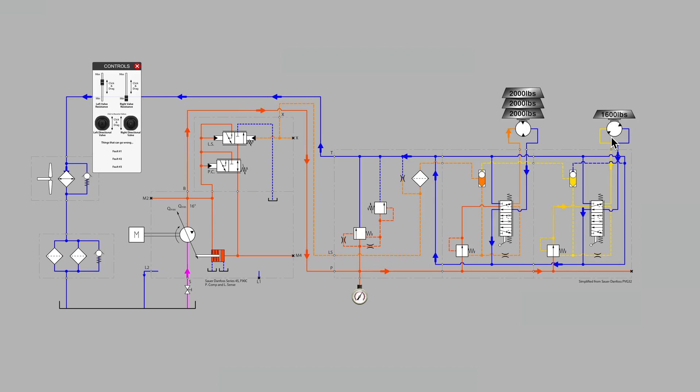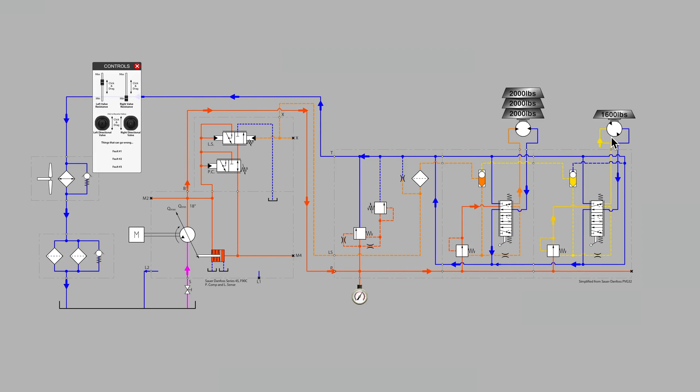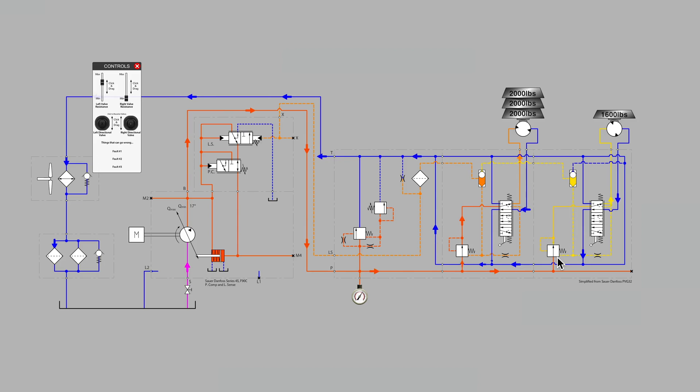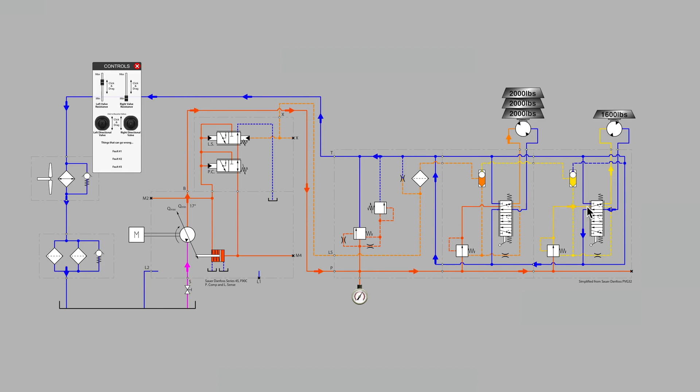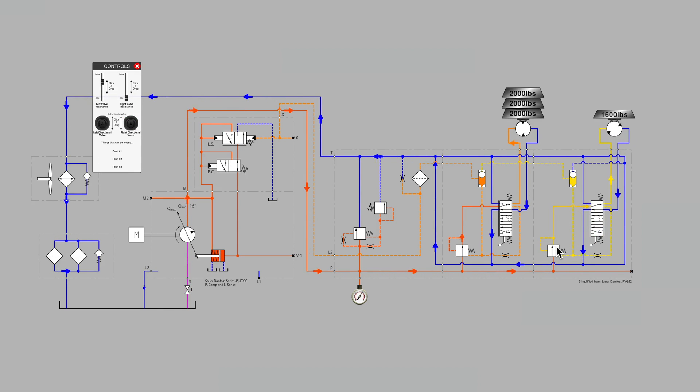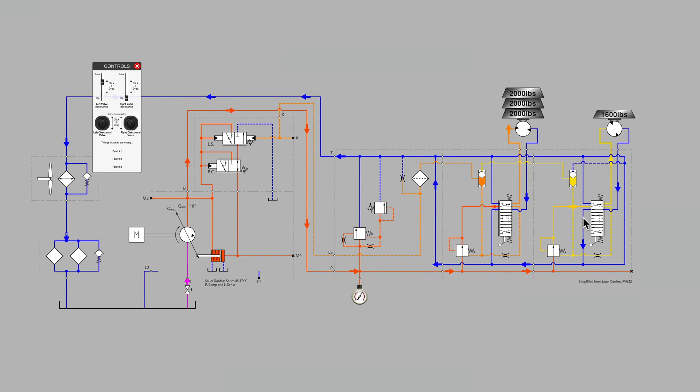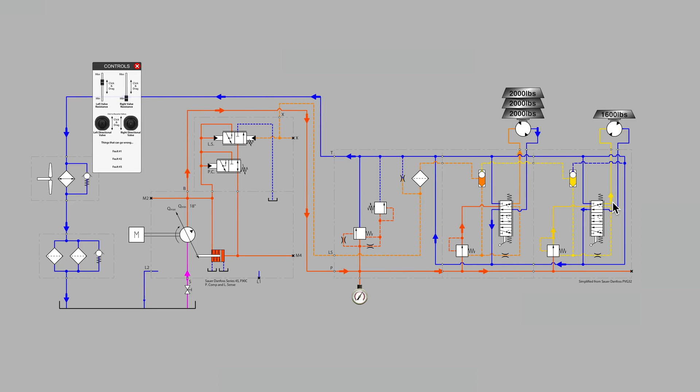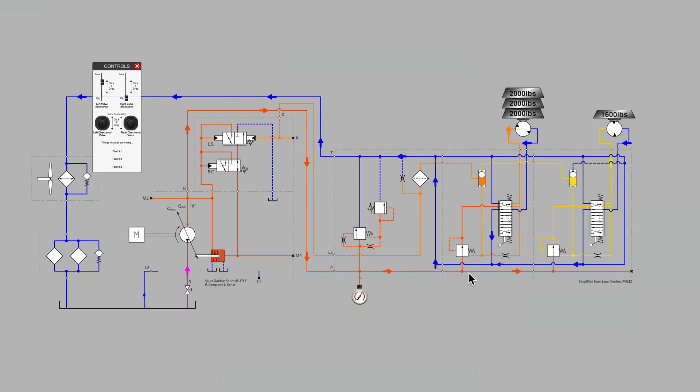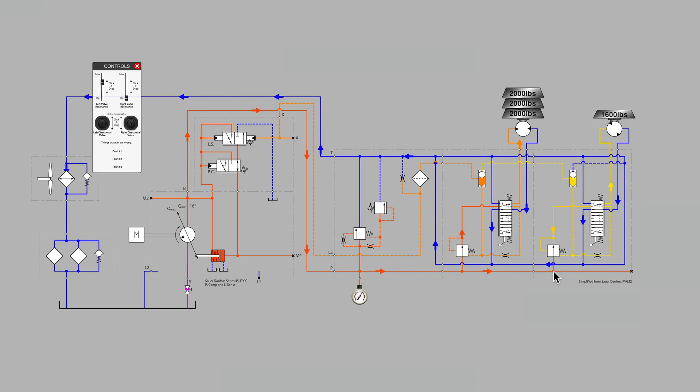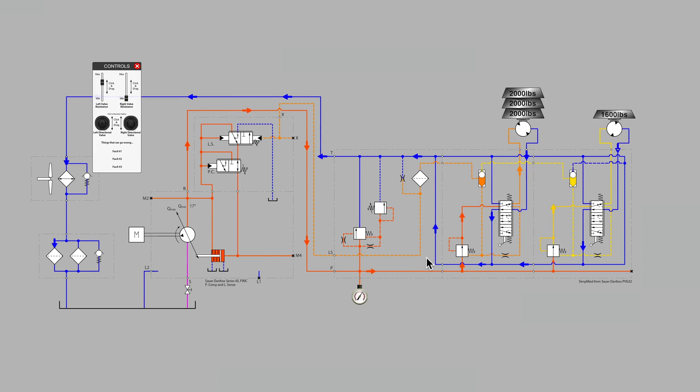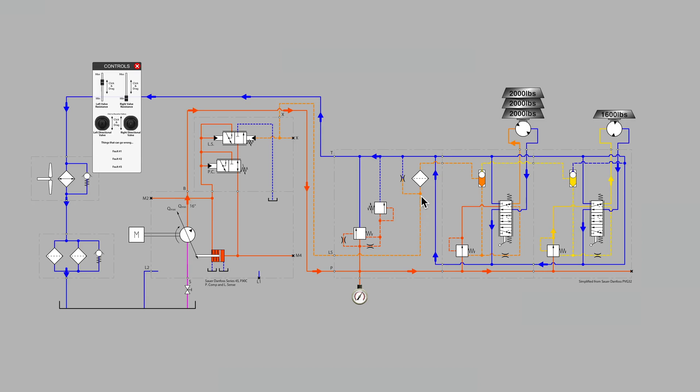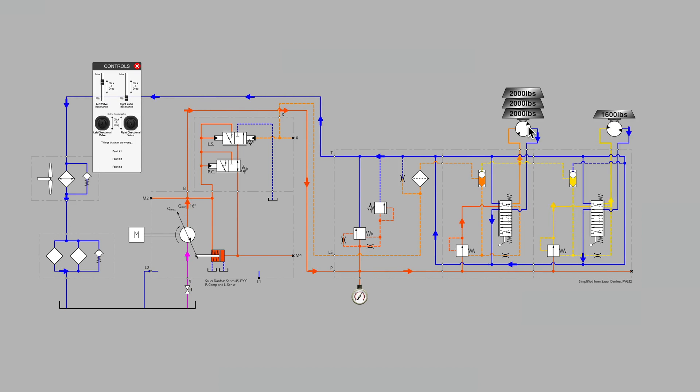That is what would surely happen if there was no pressure compensator preceding the directional control valve spool. So the pressure compensator is there to make sure that the delta P, the pressure differential across both sides of our directional control valve spool remains the same, even if our common P port line coming from the pump is now at a higher pressure because of the information that was signaled to the pump by the heavier load on the first section of the valve bank.